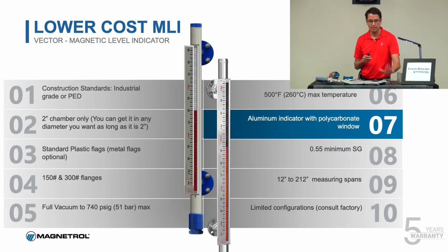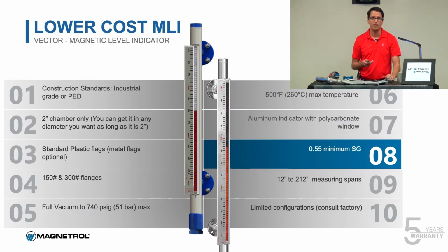Aluminum indicator with polycarbonate window. Actually, the window is polycarbonate. This is what it looks like here, and I will show you how that all works at the end. 0.55 SG minimum. If you have a very light end hydrocarbon, this device is not going to cover it, but actually 0.55 is a pretty reasonable specific gravity. If you don't know what specific gravity is, it's the relative weight of a liquid versus water. So you just take the density of a liquid, you divide it by the density of water, which is 1 or 0.99, and you get your SG.